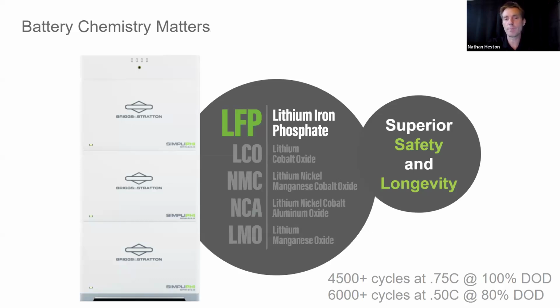Let me give you an example of why this matters. Suppose you've got a system with a generator integrated, and you'd like to use that generator to charge up the batteries when they get low, then shut the generator off so you're not using expensive fuel. If you can charge and discharge your batteries quickly, with a high C rate, you could keep that generator on for a short amount of time - say 2 hours to charge your batteries from 0% to 100%, then shut the generator off quickly. And then you have the ability to discharge your batteries from 100% again, with the generator off.